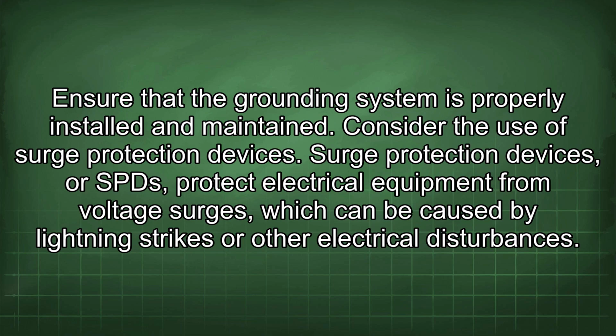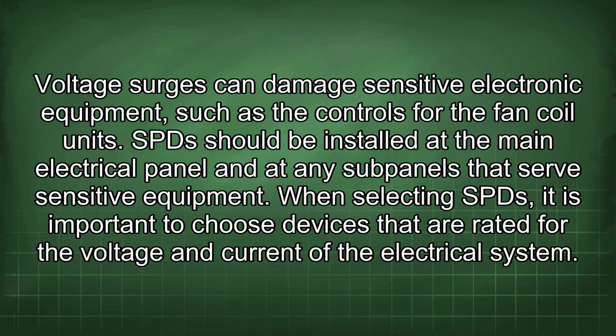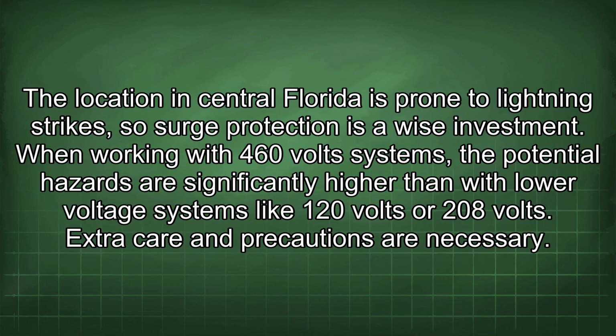Consider the use of surge protection devices. Surge protection devices, or SPDs, protect electrical equipment from voltage surges, which can be caused by lightning strikes or other electrical disturbances. Voltage surges can damage sensitive electronic equipment, such as the controls for the fan coil units. SPDs should be installed at the main electrical panel and at any subpanels that serve sensitive equipment. When selecting SPDs, it is important to choose devices that are rated for the voltage and current of the electrical system. The location in Central Florida is prone to lightning strikes, so surge protection is a wise investment.